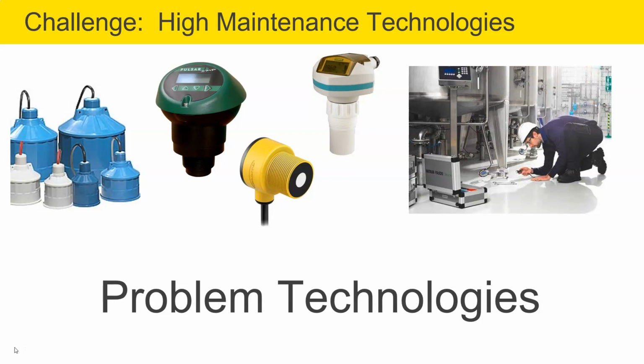Weight scale is another method people sometimes use to try to determine how much product is in a tank. Sometimes they work great. Sometimes they drift or get built up and become inaccurate and unstable. They are expensive though, and just like ultrasonics, they require annual calibrations to keep them working properly. That's extra money you don't have to spend when using radar, since radar never requires calibration.